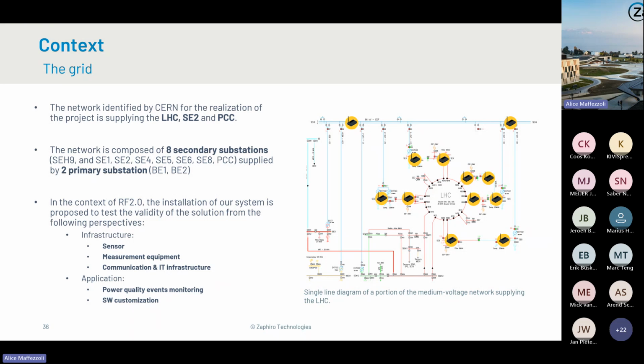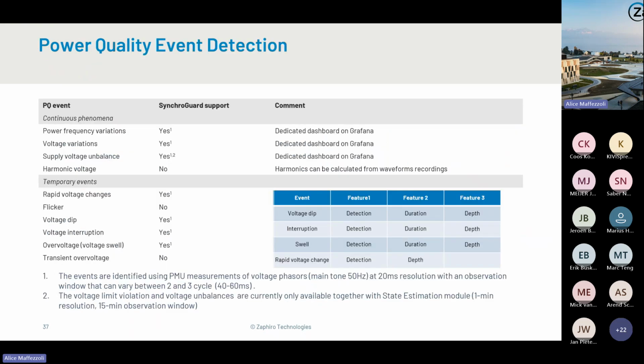The time synchronization is done through a GPS signal, so we have antennas installed outside the substation, and thanks to the GPS signal we can do the time synchronization. On top of that, we have SCADA integration, which integrates alarms and information about events, and then our own dashboard can be opened to go more in detail about the power quality event.